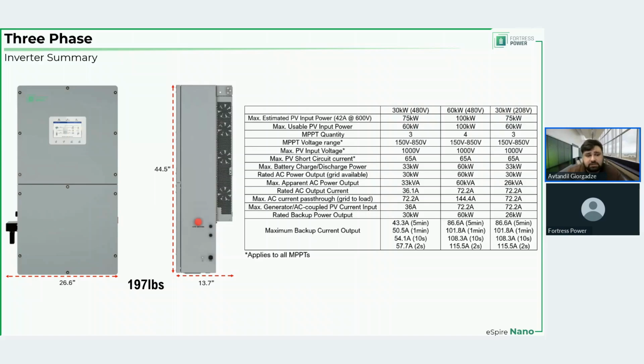So for now, generator or AC coupled PV must be equal to or less than the total backup kVA output of all the inverters working in parallel. That is continuous kVA, because as you see right here, for brief periods of time, the inverters can output more current than their continuous rating suggests. And you can see the numbers right here, which is a good perk, really, but I would not necessarily rely on it too much, because again, these are for limited periods of time.